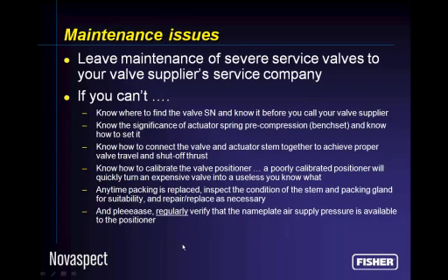And please, this is one of my pet peeves, and I go past my critical valves in plants that I've sold valves to, and I look at the pressure gauges that show the supply pressure to the positioner. If you don't have the right air pressure, as defined in the nameplate, delivered to the positioner that's on the valve, you're going to end up with a valve that's either A, not going to stroke all the way, or B, it's going to leak through in short order, and you're going to be very disappointed with the lifetime of your severe service valve. So please make sure the air supply is appropriate.